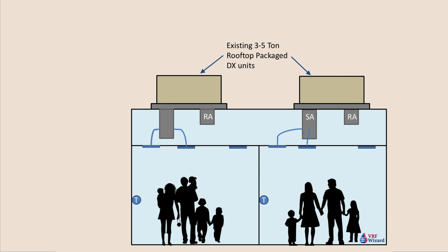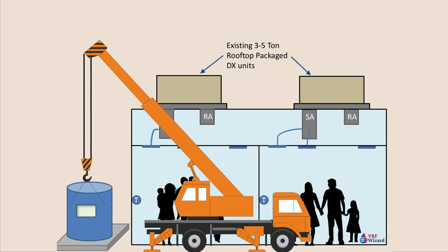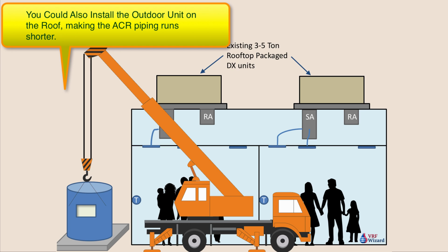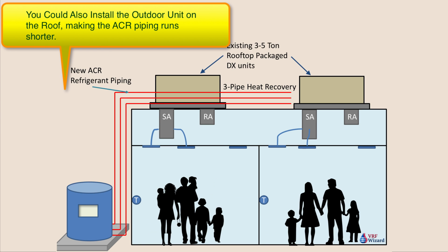But now, with this new technology or this new designed unit, you can replace existing rooftop package units with a new VRF package unit. What you would do is pour yourself a new concrete pad in order to keep the existing system running as long as possible, and then drop your VRF outdoor unit in preparation of the removal of the existing old packaged DX units in order to go to new VRF units. Then you would run your new ACR refrigerant piping.